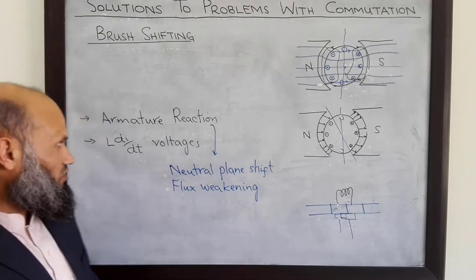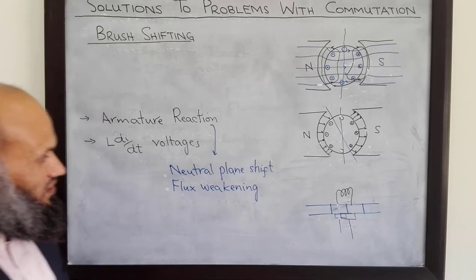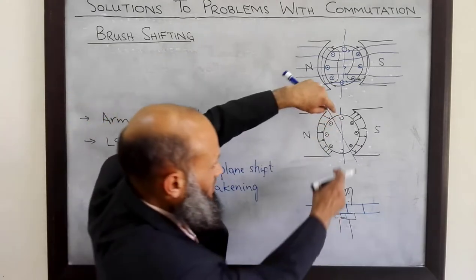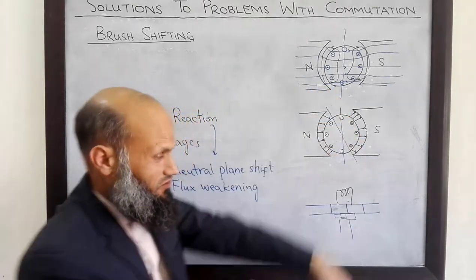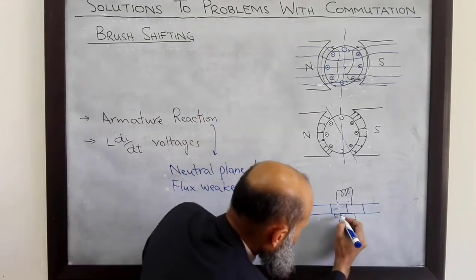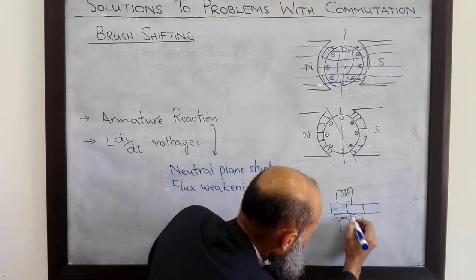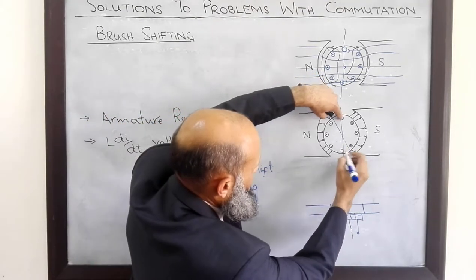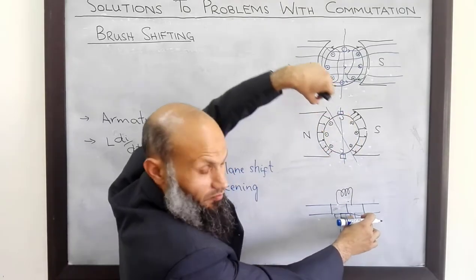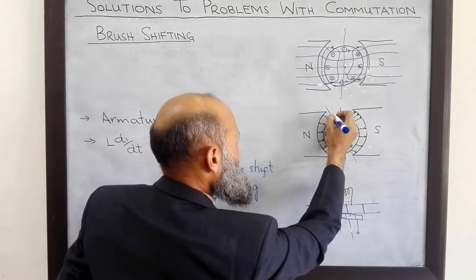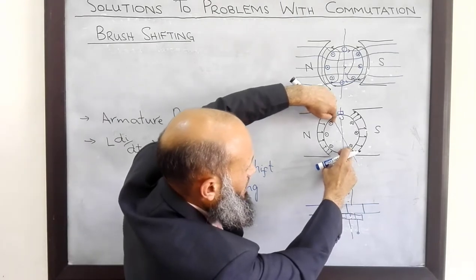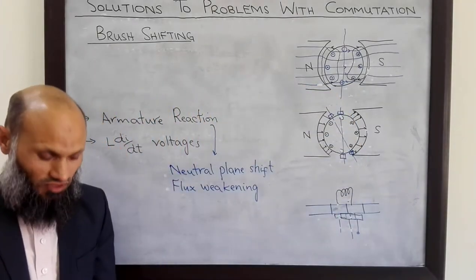So where is the possible solution? One possible solution is brush shifting. Instead of placing the brushes at the original location, we place the brush at a new location corresponding to the shifted neutral plane. So instead of shorting the coil at the old position, we move the brush to a new position. Now the coils being shorted will be at the new neutral plane location, and low voltage will be induced in those coils.